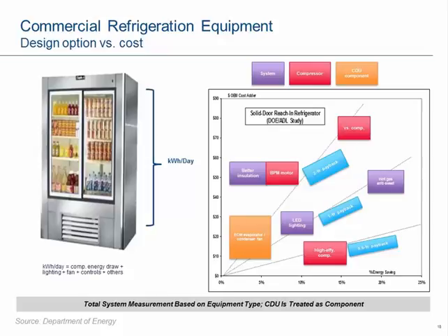The trick here is that equipment manufacturers are looking for the design options that give them the biggest bang for the buck in terms of energy savings. In study after study, you can see the high-efficiency compressor comes out as the number one design option that gives you the most energy savings for the least added cost. Other options, depending on the configuration of the piece of commercial refrigeration equipment, such as lighting and controls, can also have a really good payback, as can different things you can do with your evaporator fan motors. All of these design options are being considered by the equipment manufacturers. It's just a matter of how much energy savings they need to get and how much they're willing to pay for it.